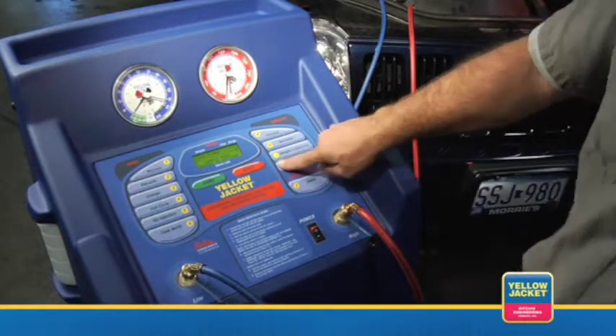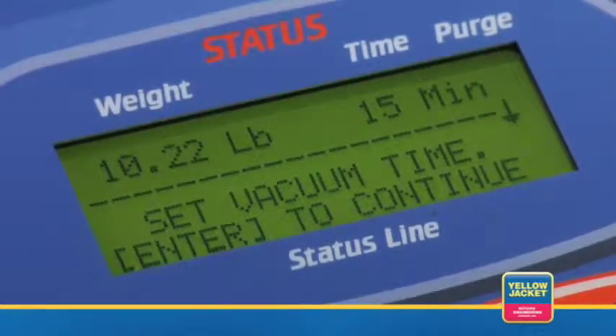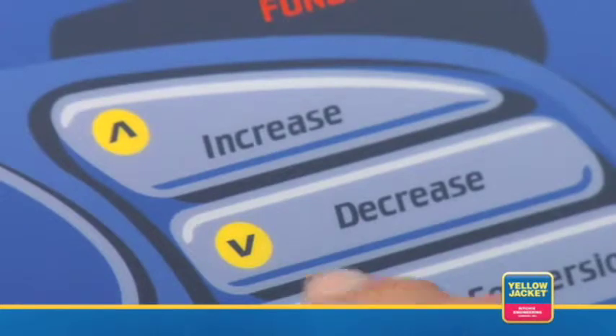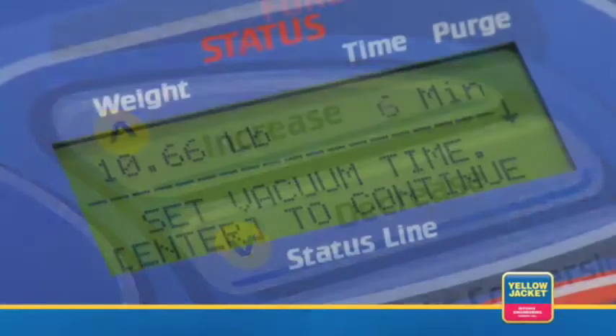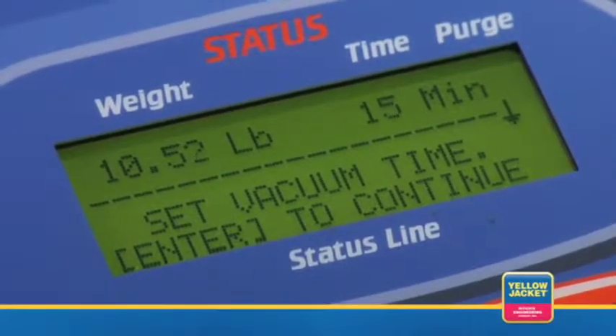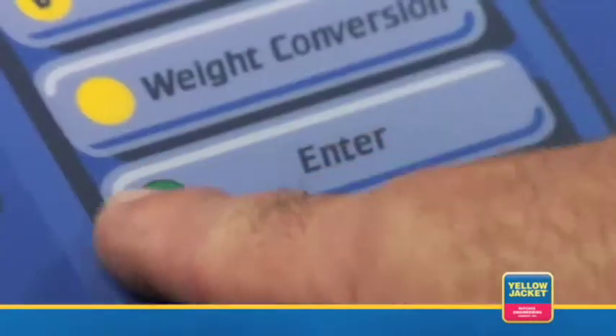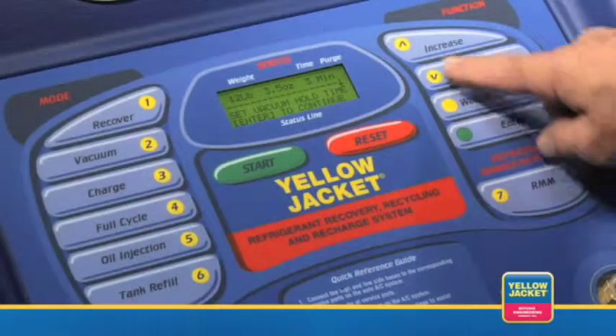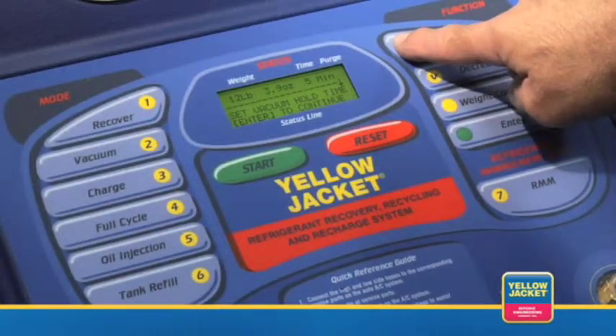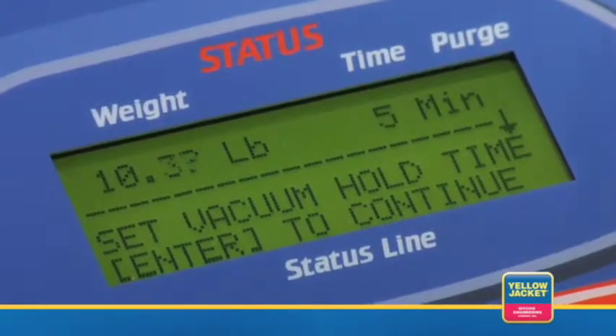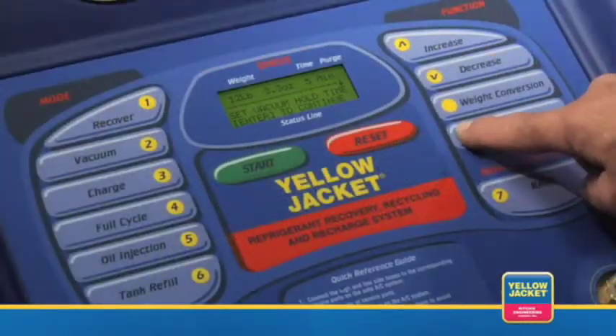When the LCD reads Set Vacuum Time, set the vacuum time by pressing and holding increase or decrease until the desired time is shown. Release the button and press Enter. Next, the LCD should read Set Vacuum Hold Time. Use the increase or decrease keys once again, setting your desired value, and press Enter. If you set the vacuum hold time to 0, the 37880 will simply skip this part of the full cycle.